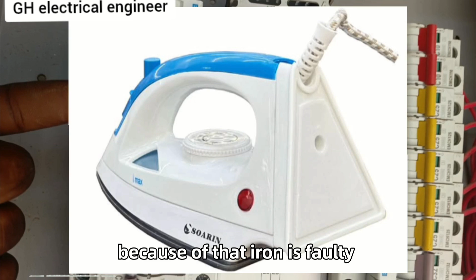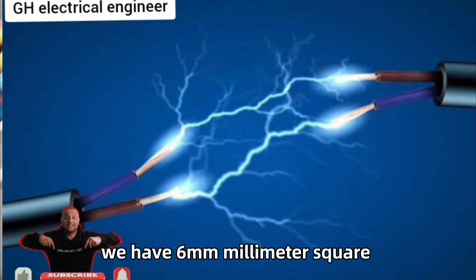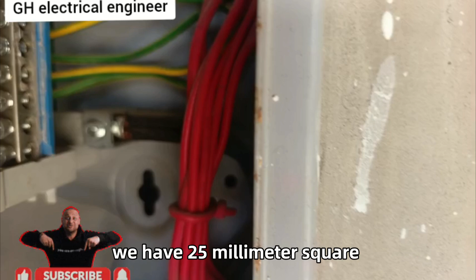These breakers are designed with a specific current - they are not constant current; different currents pass through based on the electrical wiring, because in electrical wiring the cables come in different sizes: 1.5 millimeter square, 2.5 millimeter square, 4 millimeter square, 6 millimeter square, 10 millimeter square, 16 millimeter square, 25 millimeter square, and so on.